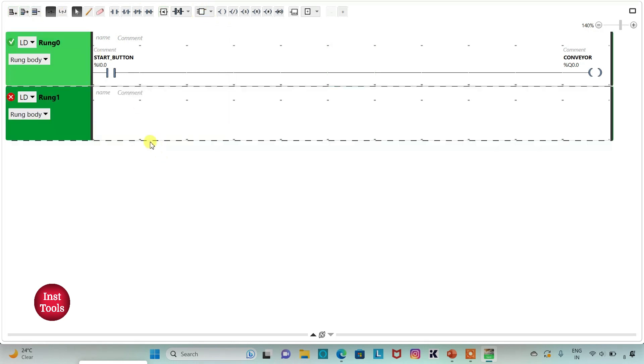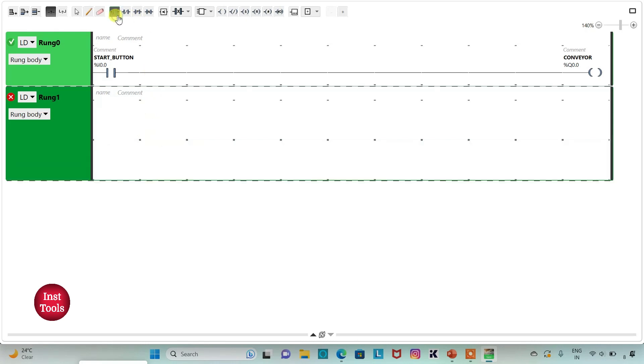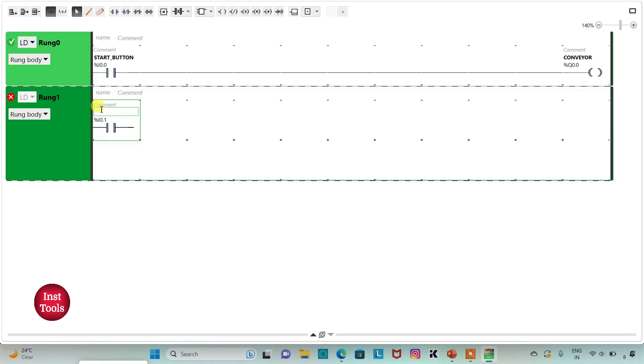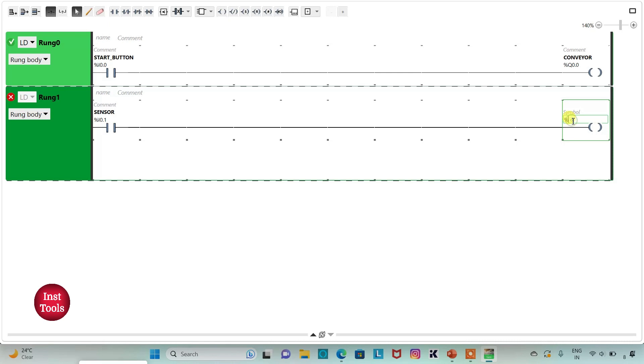We will add a new rung here. And then I will insert a normally open contact. I will assign address to it as I0.1. I will also add a symbol to it as sensor, which will detect the defect. And then I will insert a coil here. I will assign address to it as M0.0, which is a memory bit. So when the sensor will be on, the memory bit will be on — that is, when a defect is detected by the sensor, the memory bit gets true. And we will use this memory bit to turn off the conveyor.